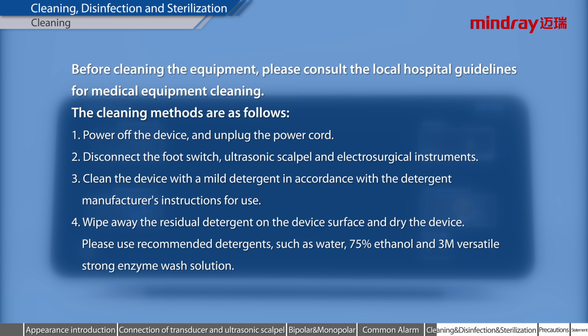1. Power off the device and unplug the power cord. 2. Disconnect the foot switch, ultrasonic scalpel, and electrosurgical instruments. 3. Clean the device with a mild detergent in accordance with the detergent manufacturer's instructions for use. 4. Wipe away the residual detergent on the device surface and dry the device. Please use recommended detergents such as water, 75% ethanol, and 3M Versatile Strong Enzyme Wash Solution.